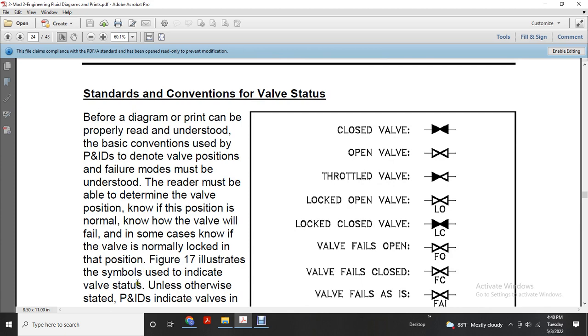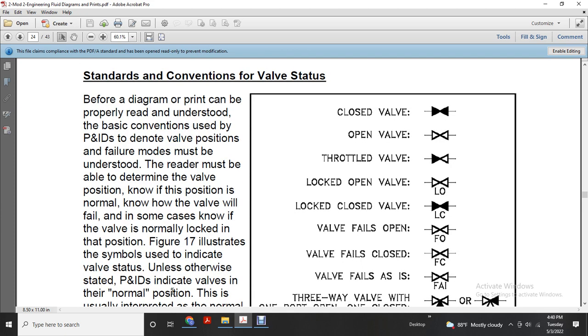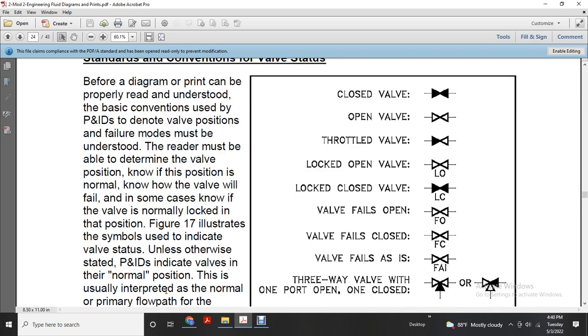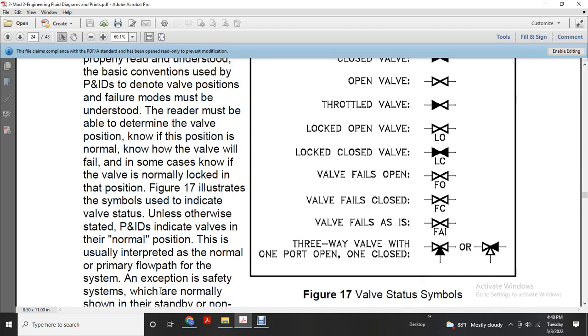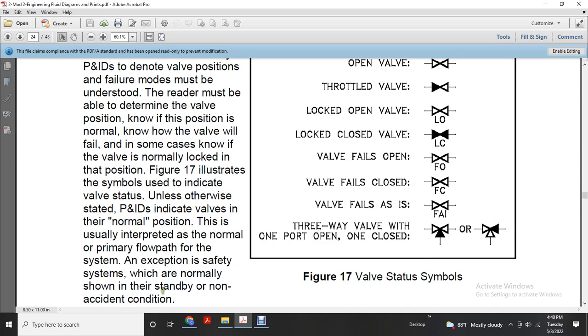Figure 17 illustrates the symbols that indicate valve status unless otherwise noted on the piping and instrument diagram drawing. The valve is shown in its normal position, usually interpreted as the normal or primary flow of the system, with the exception of the safety system, which is normally shown in a standby or non-accident condition.